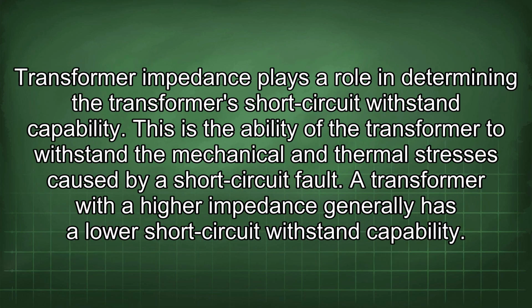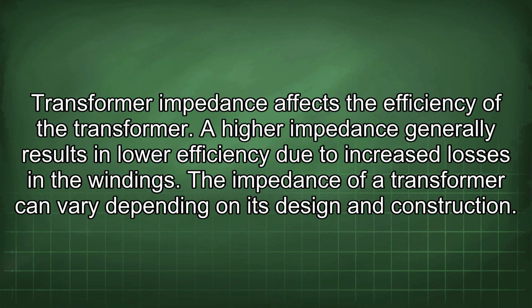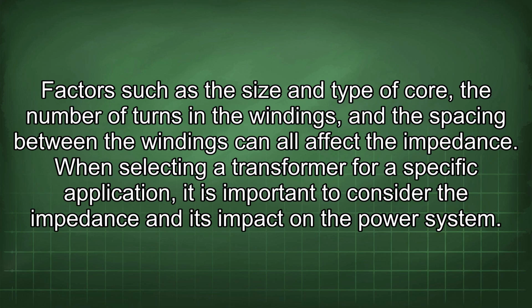Transformer impedance plays a role in determining the transformer short circuit withstand capability. This is the ability of the transformer to withstand the mechanical and thermal stresses caused by a short circuit fault. A transformer with a higher impedance generally has a lower short circuit withstand capability. Transformer impedance affects the efficiency of the transformer. A higher impedance generally results in lower efficiency due to increased losses in the windings. The impedance of a transformer can vary depending on its design and construction. Factors such as the size and type of core, the number of turns in the windings, and the spacing between the windings can all affect the impedance.